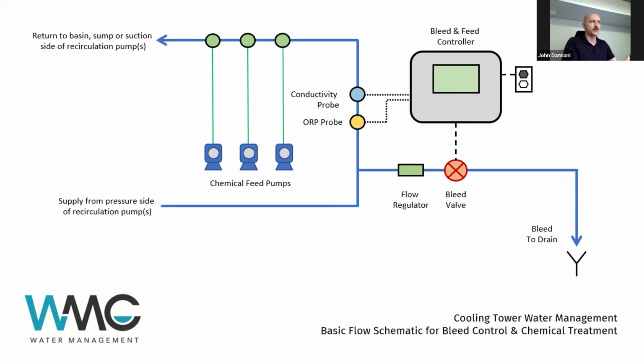This is the most simple way that you can show it. Okay, so the main thing we have here is highlighted in blue now. And what this is, we would just call this a loop. And all we need to do is get flow through the system, through a couple of sensors, to be able to measure what we're looking for in the system and decide what we need to do. Okay, so we need a live sample. We can't just drop a probe in the basin, for example, because then we don't know if the system's on or off. So we need some flow through the system.